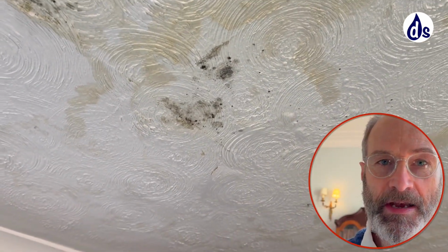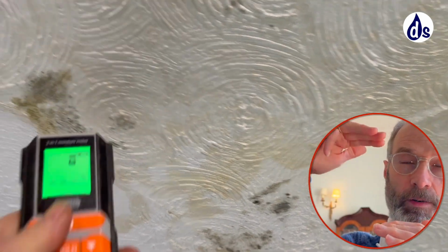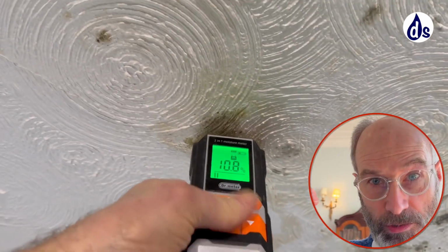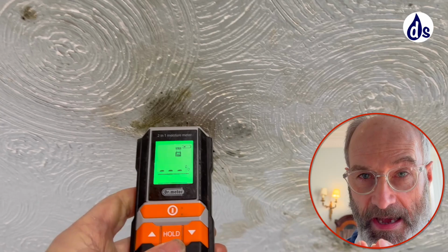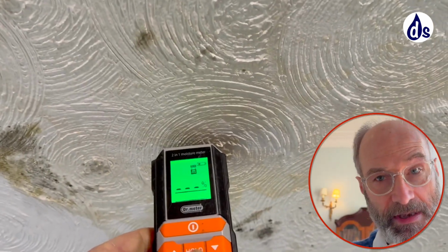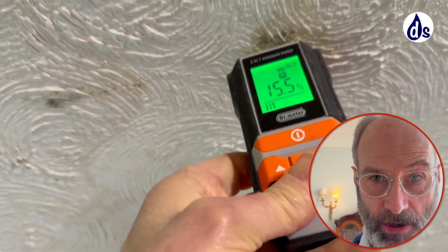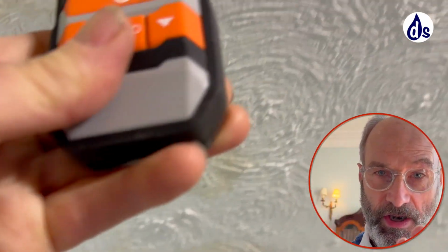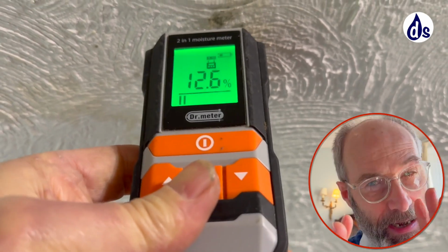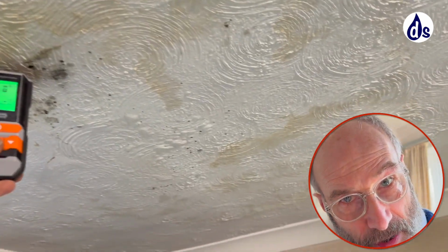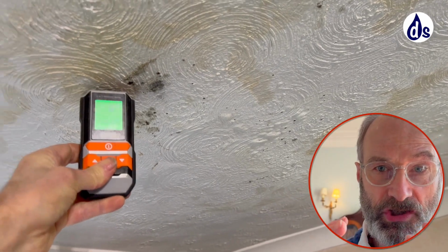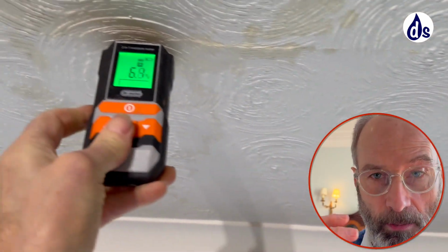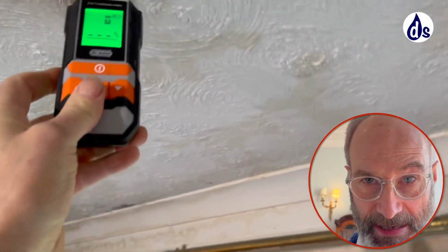So we're going to start with flat 12, and there's some brown patches at the top on the ceiling, and there's mould. Where you've got mould, you can either have a general issue with mould, caused by excess vapour across the whole property, made worse by heat loss, or you can have localized mould. In this case, I would say it's primarily localized, but made worse by general excess vapour, because the whole building is really badly ventilated.